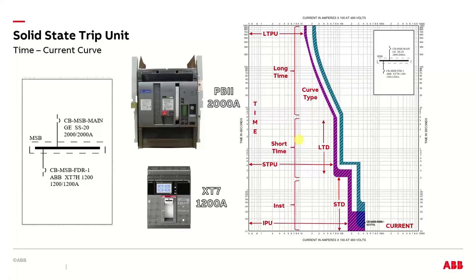So again, if you have a 100 amp breaker, but you have it on, for example, a motor load, well, you want that short time to be higher so that it allows the motor to start and get through its starting current. So you could set your short time, for example, to 6x. So that would be 600 amps. So the breaker will trip in a long time at 80, but it will wait and it won't trip unless you exceed 600 amps between this time here of a few cycles to 5 or 6 seconds to allow the motor to start.